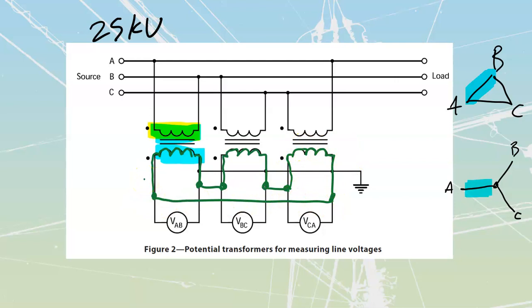And then if I were trying to measure my values of voltage, where my meters are at this point would be perfectly fine, because right now I'd be measuring across from my A to my B. I see up top, this one is A to B. Down here, this is going to be an A to B winding down here. We would want to remove this line over here if we wanted to do the actual delta type of configuration here. But that would get me, in that case, a true line-to-line value of voltage.